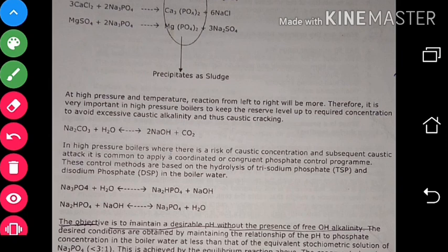This covers boiler water treatment, the steps, the purpose of each test, how each test is carried out, and what phosphate reserve means. If during a test you get high sludge or high alkalinity, perform a partial blow down or total blow down to remove impurities from the boiler water system. Please like and subscribe to the channel. If you have any doubt regarding the boiler water test and treatment, comment in the section below. Thank you.